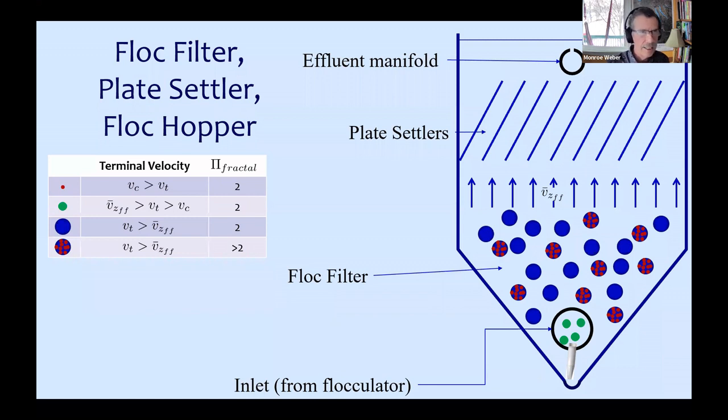I'm curious, did any of you ever see a rapid sand filter being backwashed? The water is going up through the sand so fast that the sand ends up being fluidized, it moves around. And if you were to jump into that sand filter, please don't, you would sink right into that fluidized bed because it's no longer settled, there's no structure there, it's all a fluid, even though there's sand, which is not a fluid, but it acts like a fluid.